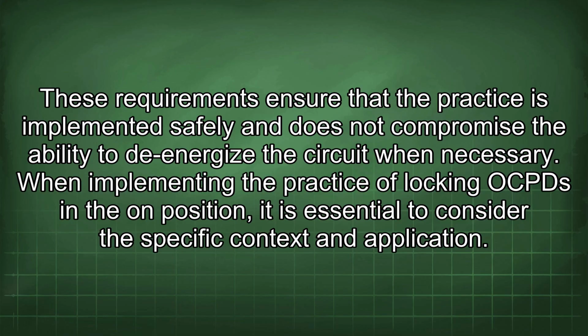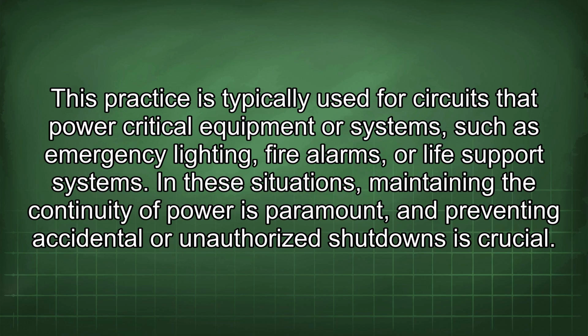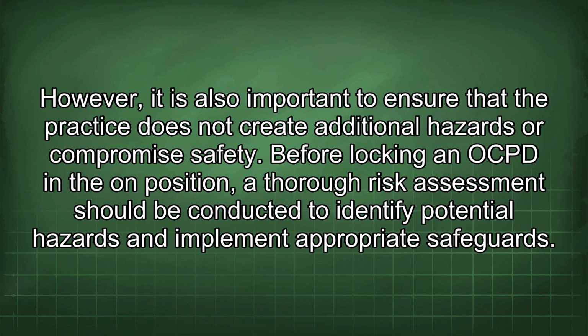These requirements ensure that the practice is implemented safely and does not compromise the ability to de-energize the circuit when necessary. When implementing the practice of locking OCPDs in the on position, it is essential to consider the specific context and application. This practice is typically used for circuits that power critical equipment or systems, such as emergency lighting, fire alarms, or life support systems. In these situations, maintaining the continuity of power is paramount, and preventing accidental or unauthorized shutdowns is crucial. However, it is also important to ensure that the practice does not create additional hazards or compromise safety.